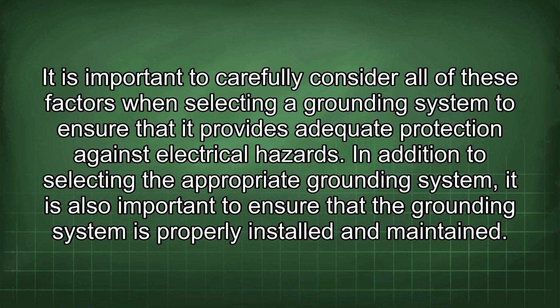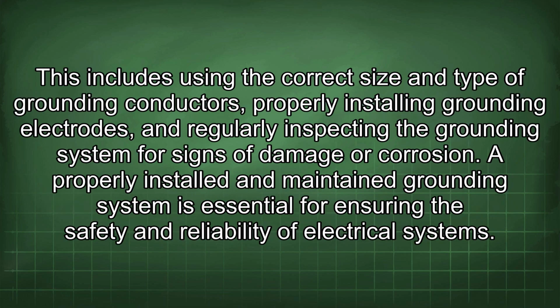In addition to selecting the appropriate grounding system, it is also important to ensure that the grounding system is properly installed and maintained. This includes using the correct size and type of grounding conductors, properly installing grounding electrodes, and regularly inspecting the grounding system for signs of damage or corrosion. A properly installed and maintained grounding system is essential for ensuring the safety and reliability of electrical systems.